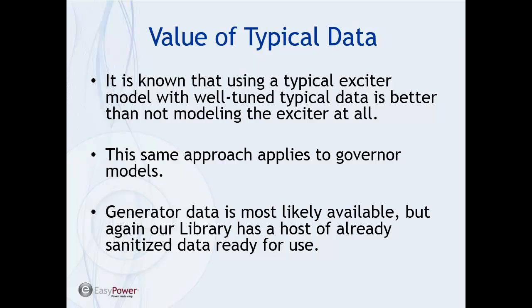Well, I will have to admit, I measured one where somebody by accident walked away and didn't tune it, so we ended up tuning it for them. But still, I would say in almost every case, the excitation system is going to be tuned for the system where it's applied. This also applies to governor models. They are going to be tuned to give as good a response as can be achieved with that particular generator.